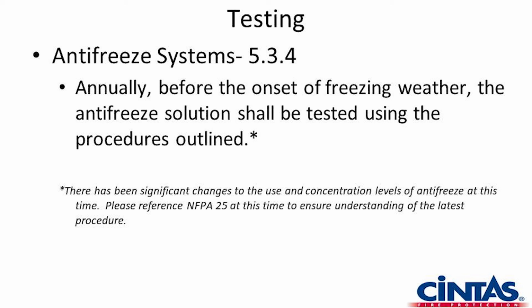We see a lot of quotes. A technician gets on site to test the antifreeze solution. He doesn't know what it is. There's no placard on the wall. He knows both of those are supposed to be present, and he writes it up as a deficiency. So depending on what state we're in, that may or may not be a requirement, so we may not have to drain the system. It goes back to the fact that across the United States, we're working from the 2002 NFPA 25 all the way through the 2020 NFPA 25. Very, very, very frustrating, but that's something we do.